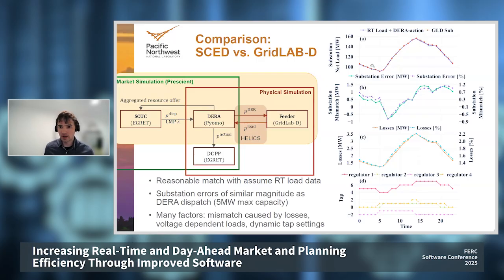On the top right plot, blue is the real-time load with DERA, our economic dispatch result, and red is GridLab-D. They follow pretty closely. If we look at the difference in the plot right below, the mismatch is about plus or minus 1%, which translates to about plus or minus 1 megawatt. It's not too large, although that is a reasonable percentage of this 5 megawatt DERA capacity.